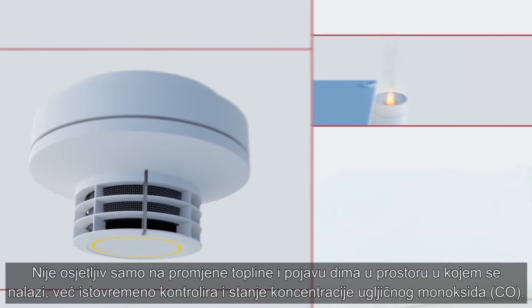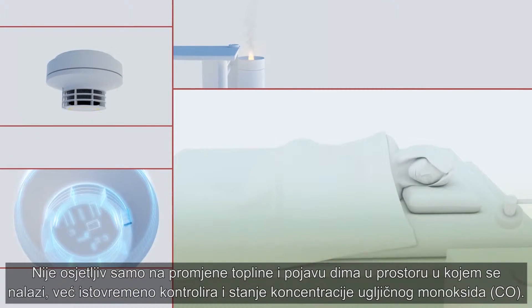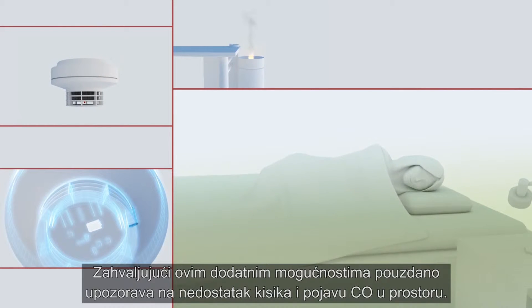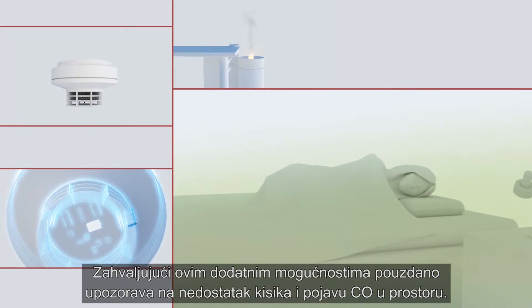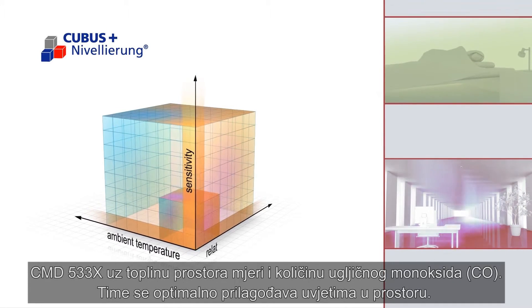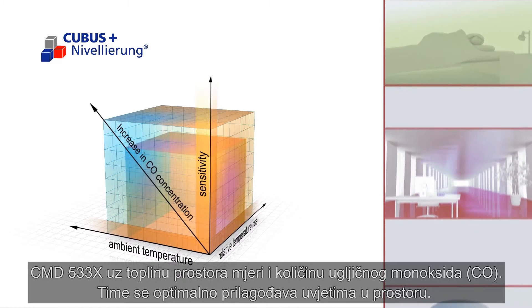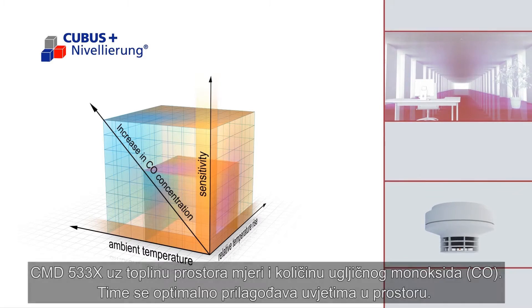The Integral CUBUS CMD533X multiple sensor detector is another new development. It does not only monitor the increase of temperature and or smoke in a room, but it also monitors the concentration of carbon monoxide, CO. Thanks to this additional sensor, the detector also protects humans from the danger of suffocation. Especially during sleep, the presence of the odorless CO cannot be recognized. In addition to measuring the ambient temperature, the CMD533X also measures the carbon monoxide, CO, concentration.